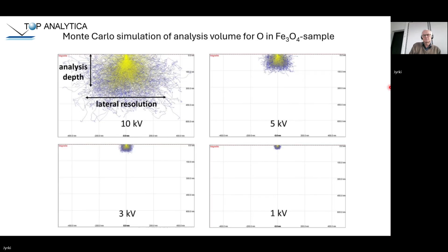Here is a more accurate calculation after these Monte Carlo simulations. Lateral resolution is now defined as the spot diameter where 90% of the X-ray intensity is detected, and analysis depth is the depth where 90% of the X-rays are coming from. We can see that decreasing the voltage will improve the lateral resolution and also the surface sensitivity. EDS, or generally X-ray analysis, is relatively surface sensitive, so 1 nanometer layers or even monolayer thick layers can be easily detected with X-ray analytical methods in a scanning electron microscope.